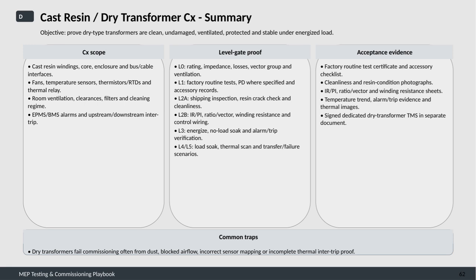Level 3 involves energizing the transformer, conducting no-load soak tests, and verifying alarms and trips. The final levels, 4 and 5, focus on load soak tests, thermal scans, and simulating transfer and failure scenarios to confirm stability under real operating conditions.